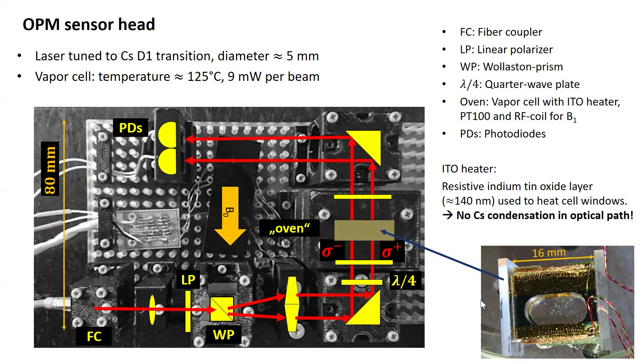These beams enter the so-called oven, which is a thermally isolated chamber equipped with two optical windows and a B1 RF coil for generating the oscillating B1 magnetic field. Inside the oven is the cesium vapor cell, operated at around 125 degrees Celsius. This cell is equipped with an ITO heater — an indium tin oxide layer deposited on the windows — so that the windows are the hottest spot, preventing cesium condensation within the optical path.